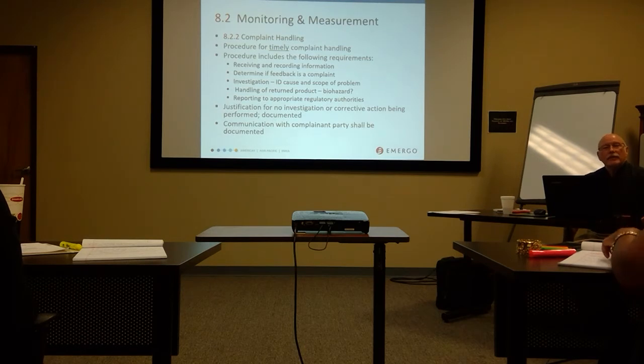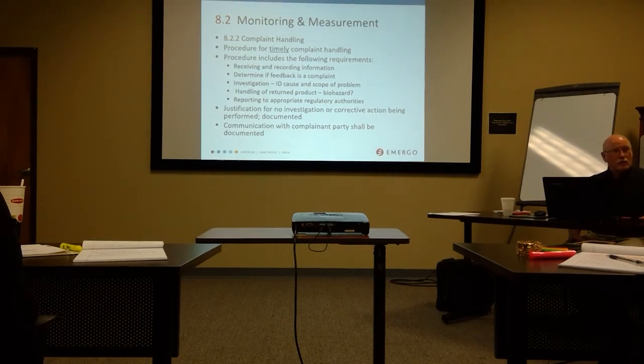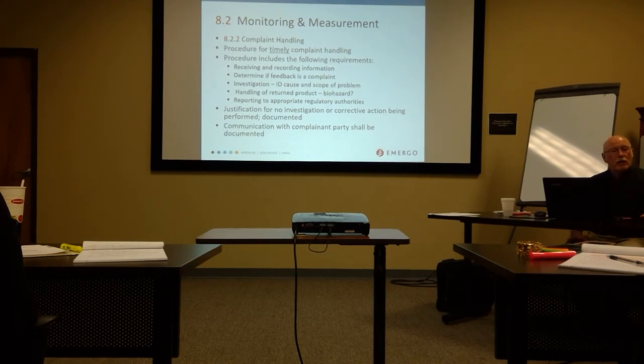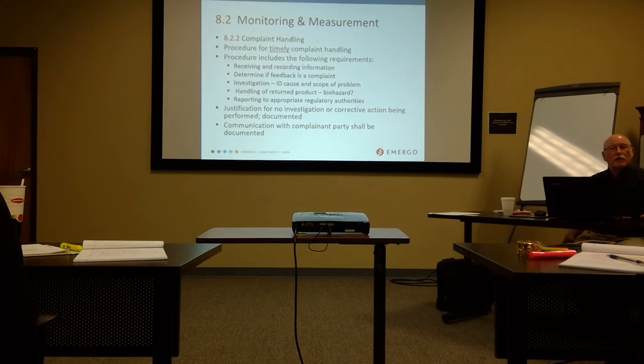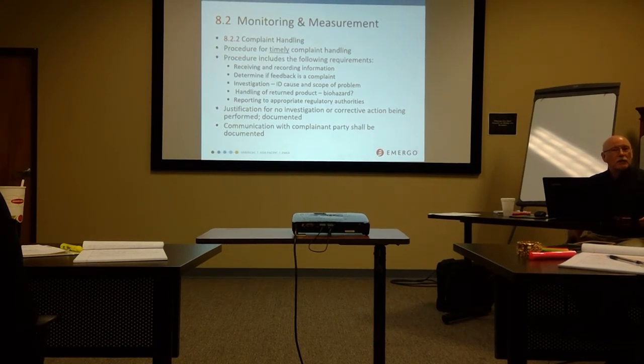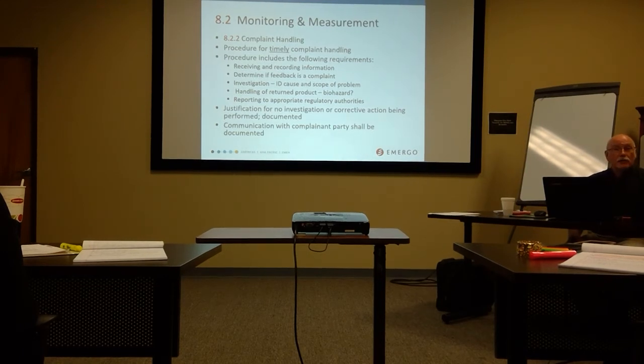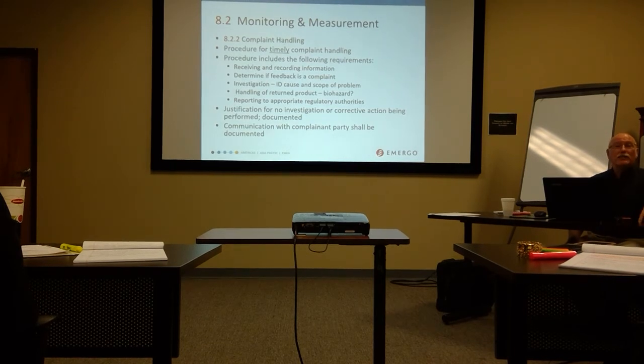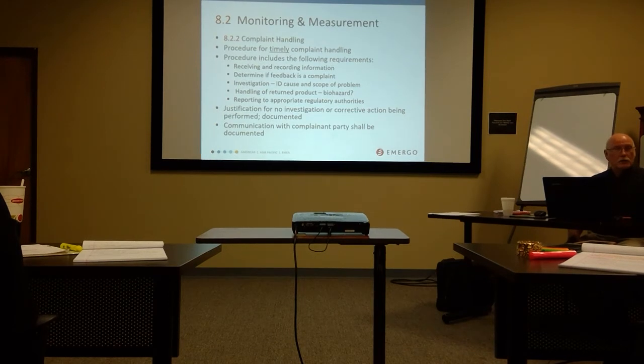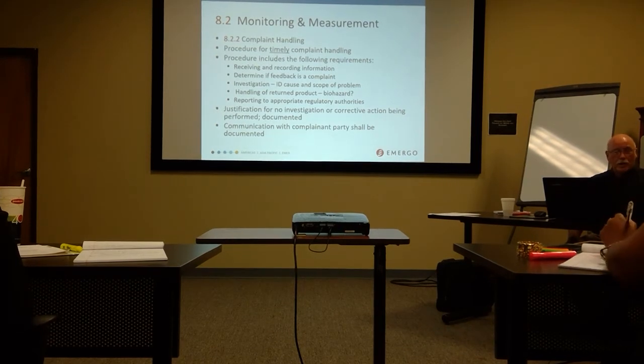Next step, investigation. Now, investigation has two elements to it that are somewhat related, and you're going to see this in CAPA also. For some complaints, I want to ask myself the question, how extensive might this problem be? If I get a complaint that the bed collapsed on somebody, then yeah, that's on a specific serial number. Have I seen any others? Do I have a trend here? Do I have a bigger problem than just this one complaint? And you'll see this parallel exactly like this in CAPA also. So some consideration over the scope and nature of this thing. Is it isolated? Is it not? If it's not, then we may need to take different and more direct action.